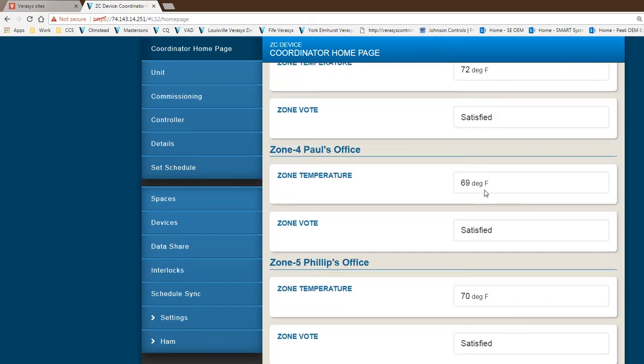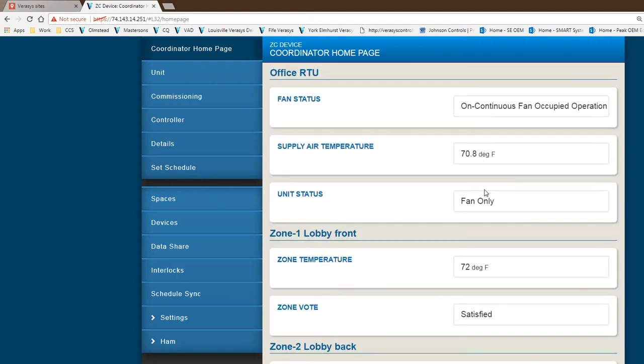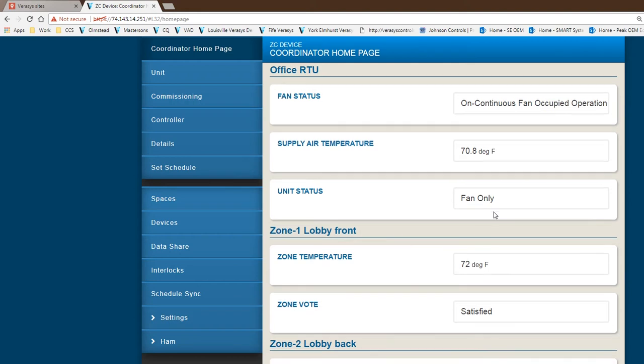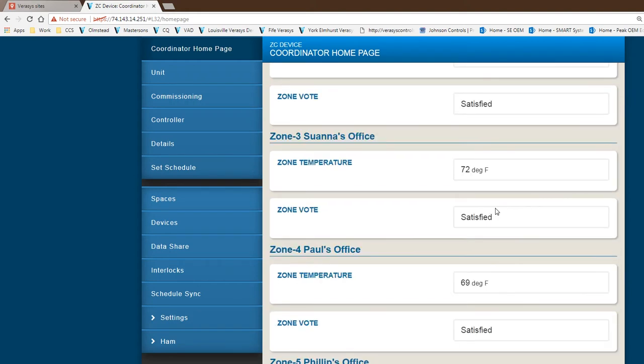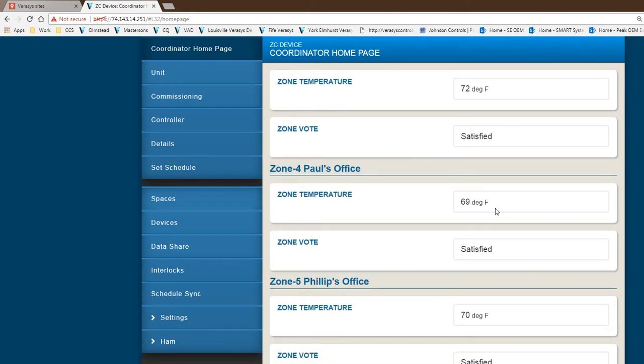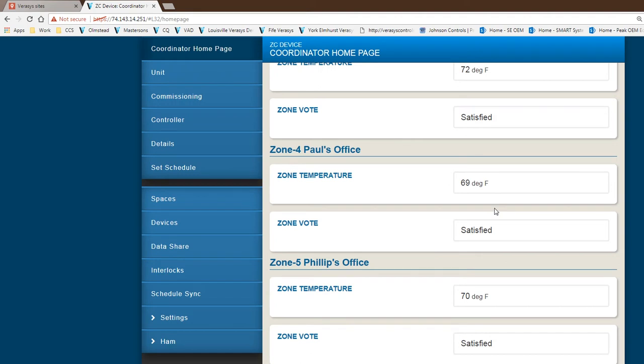That's why the fan is in only mode right now, meaning it's just fan running with no cooling and no heating. Because all the zones, this is a changeover bypass system, all the zones are satisfied. So there's no call for any kind of cooling at this point.